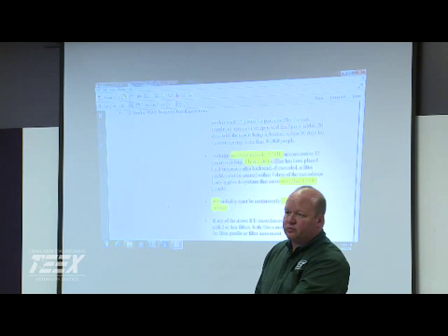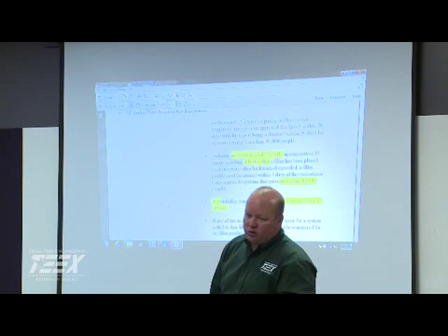We usually just go by our loss of head. There's times we'll get 6 or 7 days, and then there's times you get 2 or 3 days. The way we were treating, we really didn't have a big issue of loss of head or turbidity issues, so it was runtime. We just set up runtime like 96 hours, and that's when we would do our backwashes.